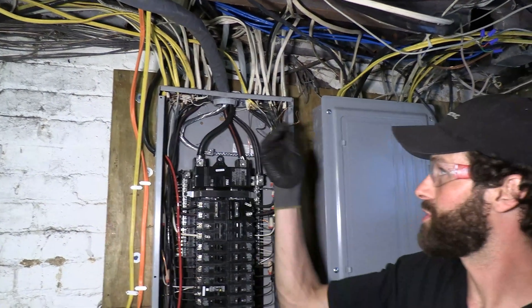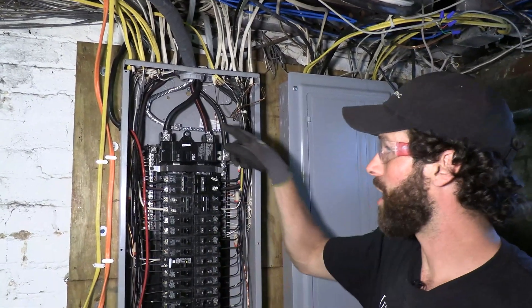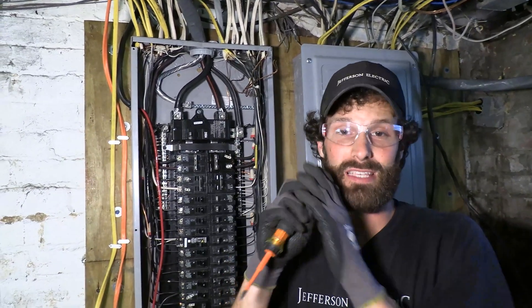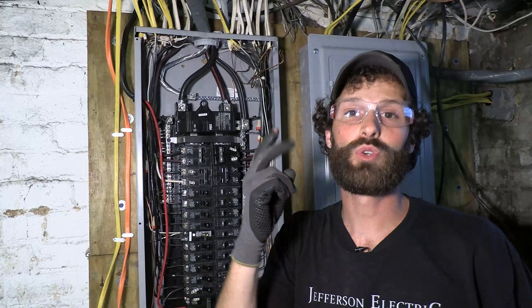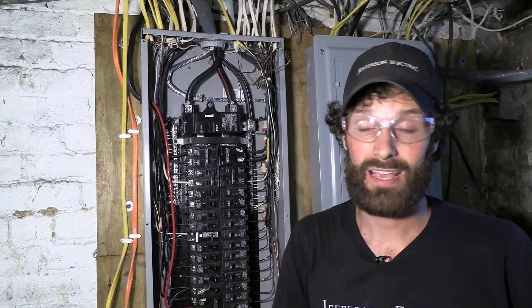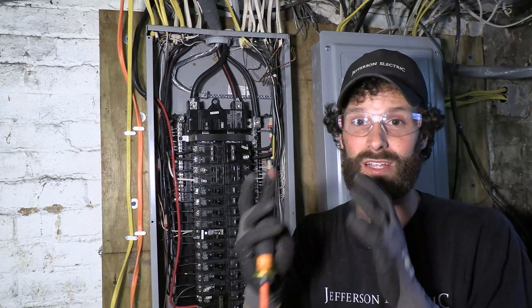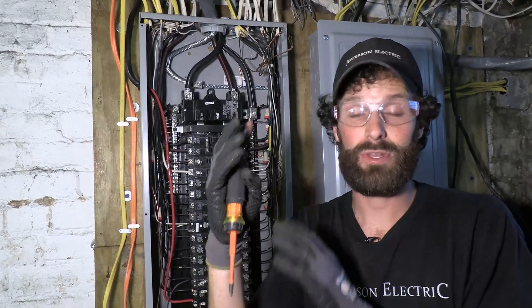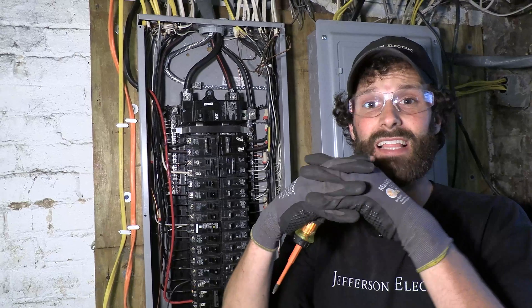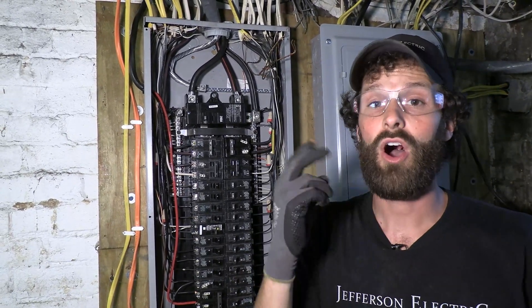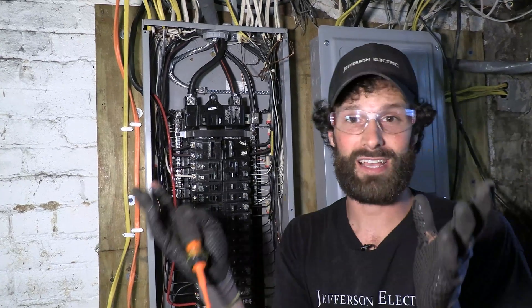The only time you can put two grounding conductors on one terminal screw is when the terminal screw is explicitly rated for two or more conductors of that size. If you are putting two conductors, never put two dissimilar conductors together, i.e. aluminum and copper. That dielectric union will cause corrosion potentially overheating.